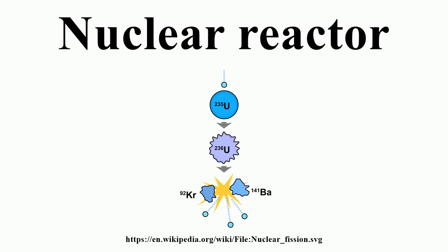Xenon-135 accumulation can be controlled by keeping power levels high enough to destroy it by neutron absorption as fast as it is produced. Fission also produces iodine-135, which in turn decays to new xenon-135. When the reactor is shut down, iodine-135 continues to decay to xenon-135, making restarting the reactor more difficult for a day or two. The xenon-135 decays into cesium-135, which is not nearly as poisonous as xenon-135, with a half-life of 9.2 hours. This temporary state is the iodine pit.